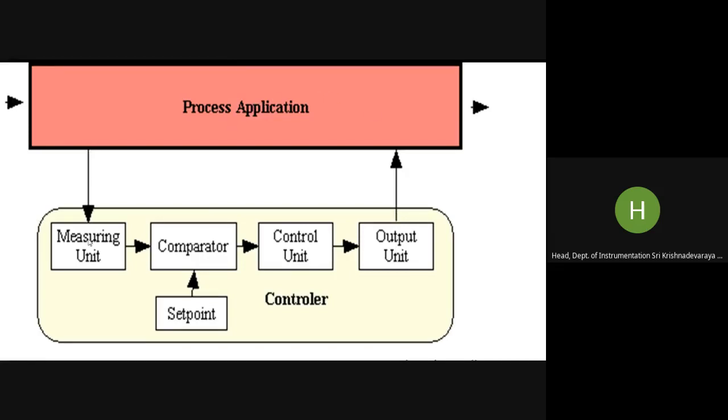So when it comes back next, it is 71 degrees centigrade. Again the error is -1. The control unit gives the output to reduce the steam flow so that the temperature reduces. Again, when it comes back, it is 69.5, compares it, error signal, again increases the steam, 70. So that is how the entire thing will be maintained compared to the set point.